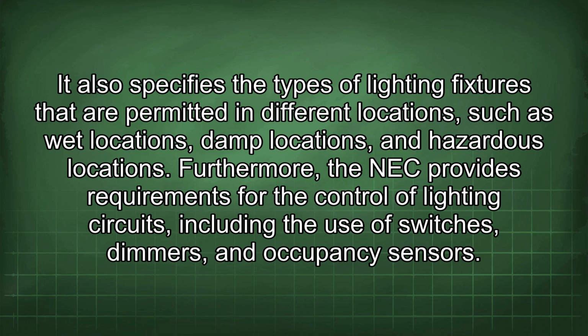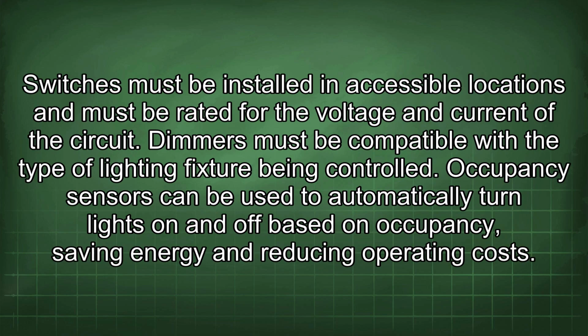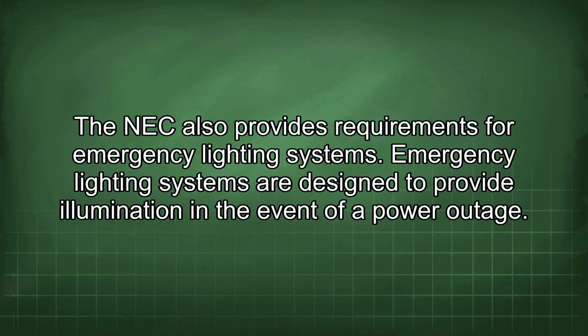Furthermore, the NEC provides requirements for the control of lighting circuits, including the use of switches, dimmers, and occupancy sensors. Switches must be installed in accessible locations and must be rated for the voltage and current of the circuit. Dimmers must be compatible with the type of lighting fixture being controlled. Occupancy sensors can be used to automatically turn lights on and off based on occupancy, saving energy and reducing operating costs. The NEC also provides requirements for emergency lighting systems.